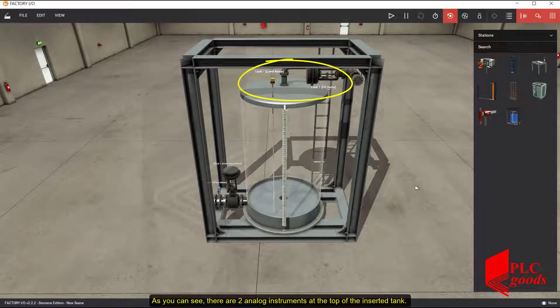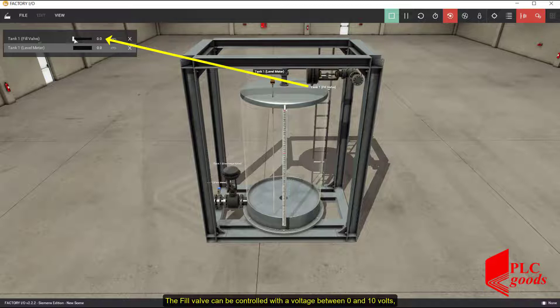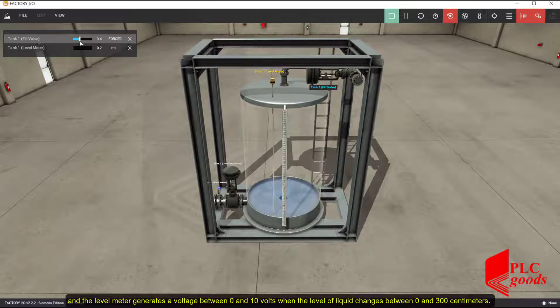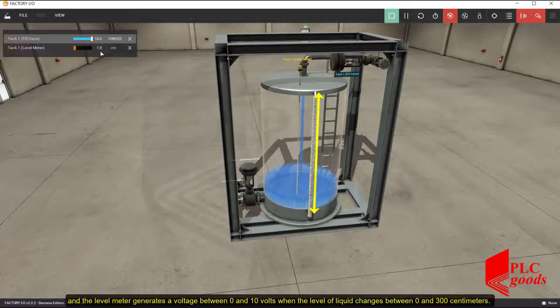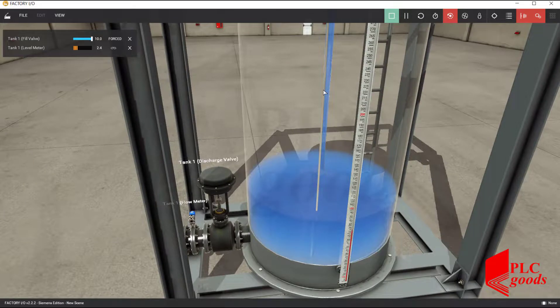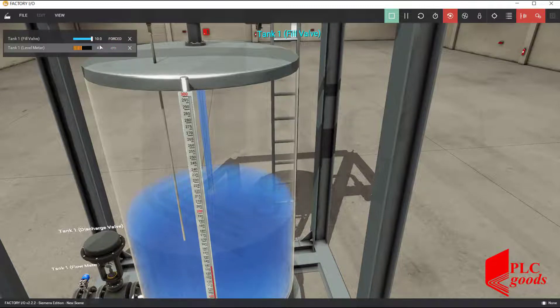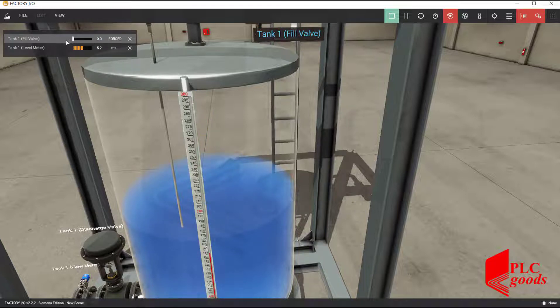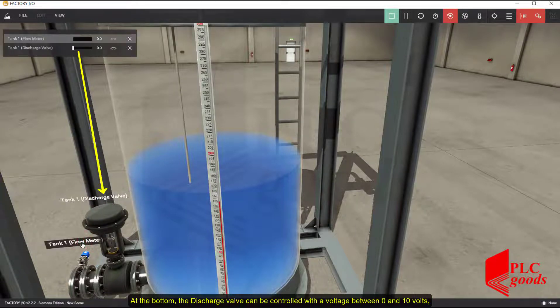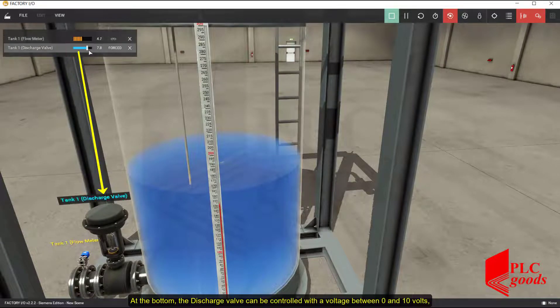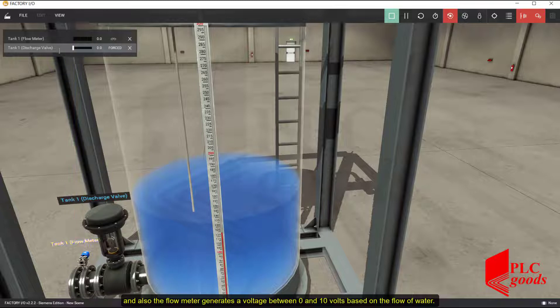As you can see, there are two analog instruments at the top of the inserted tank. The fill valve can be controlled with a voltage between 0 and 10 volts, and the level meter generates a voltage between 0 and 10 volts when the level of liquid changes between 0 and 300 centimeters. At the bottom, the discharge valve can be controlled with a voltage between 0 and 10 volts, and the flow meter generates a voltage between 0 and 10 volts based on the flow of water.